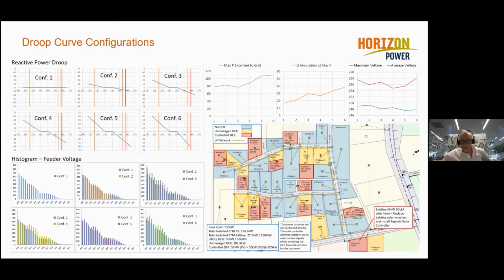And as I cycle through this visualization, what you will see is that the inverters under test actually do a really good job of absorbing reactive power and pulling the voltage down. But at the same time, they inadvertently create an operational advantage for the uncontrolled inverters, who then raise the voltage back up again so that they can export more power. So the result is twofold: a negligible reduction in the maximum voltage on the feeder, but an appreciable increase in the amount of renewable energy that's exported onto that feeder.